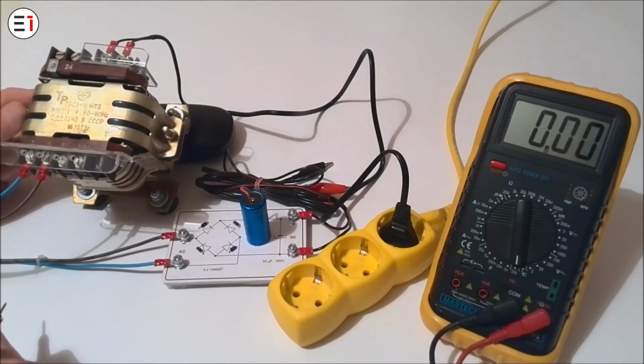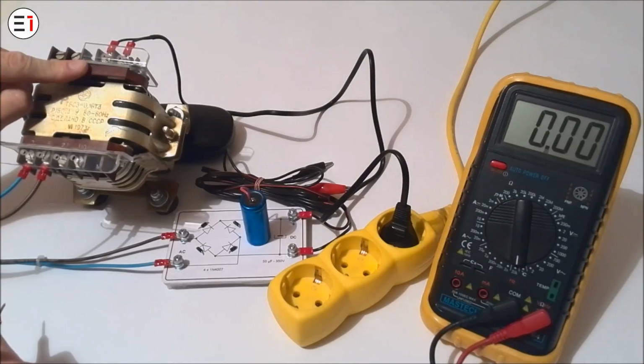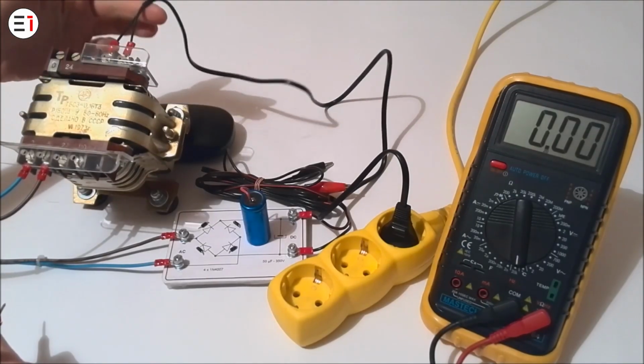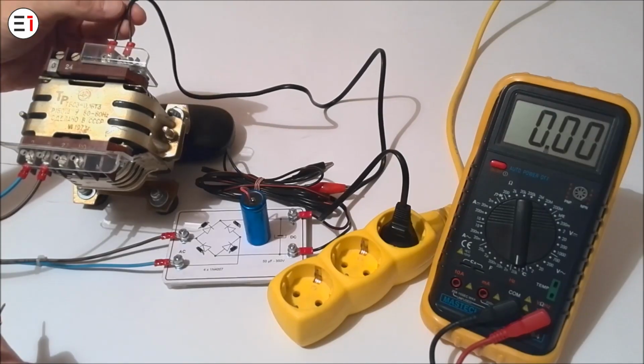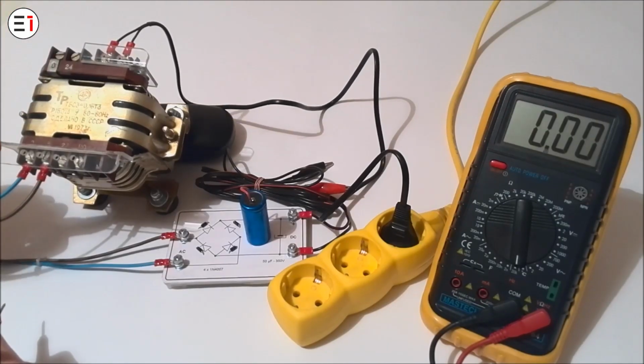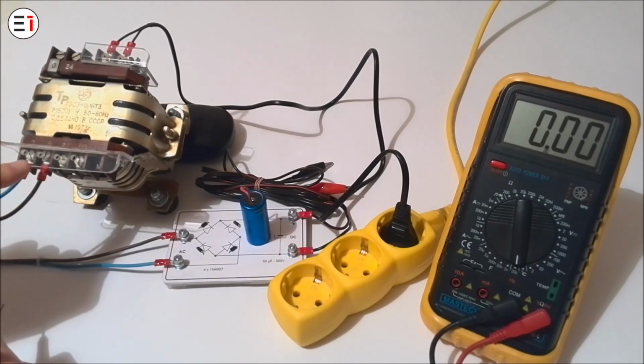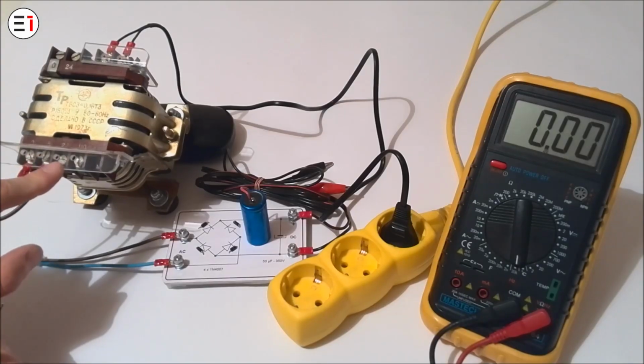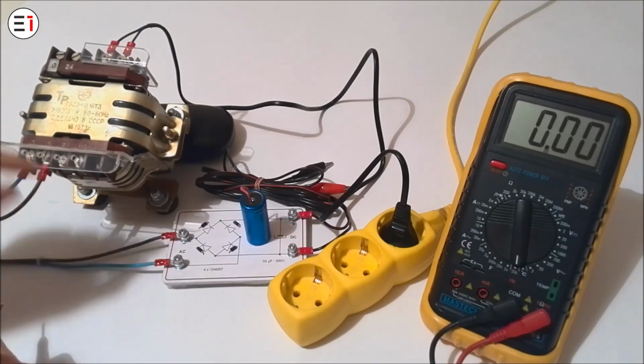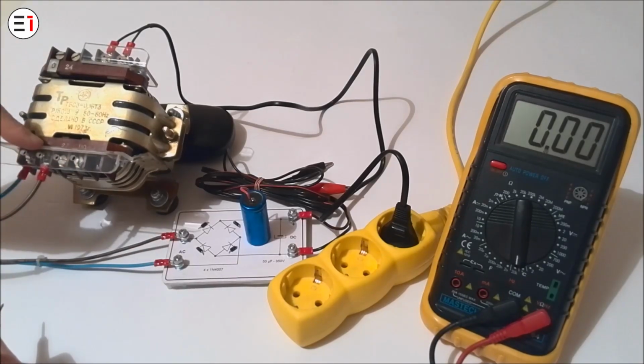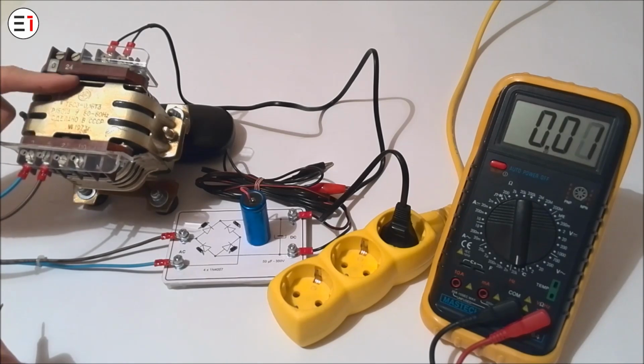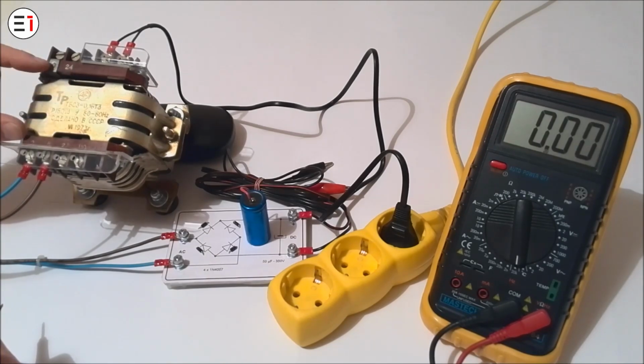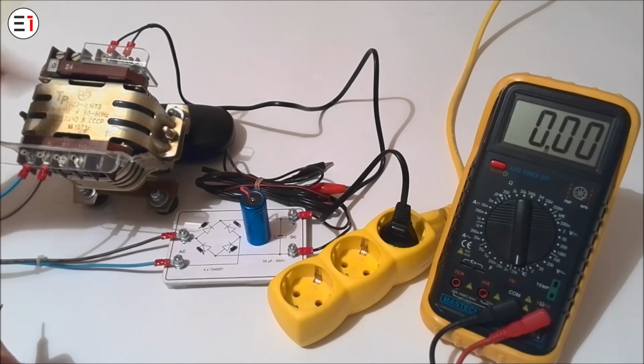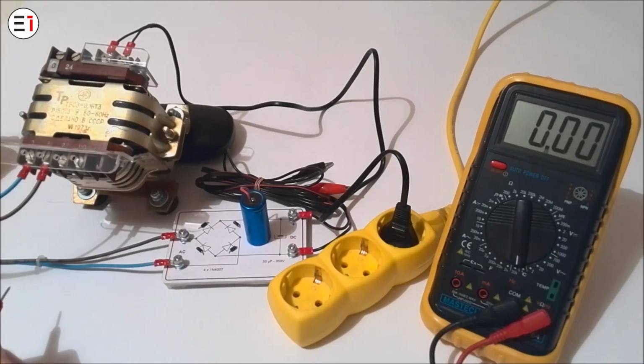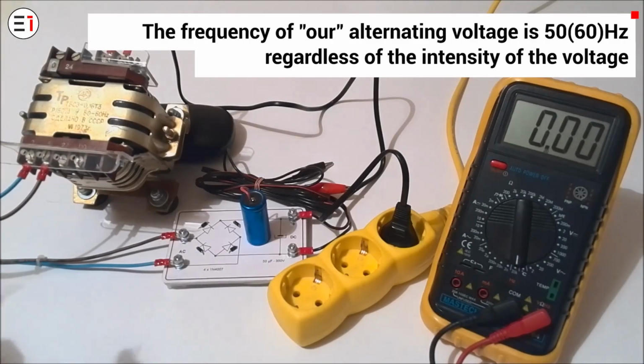Here we have a device called a transformer, and its role is to reduce the primary voltage, in this case the voltage between phase and zero, of 230 volts, to the voltage values that we can read here. Therefore, its purpose is to reduce voltages to 5 volts, 22 volts, and 110 volts. It should be known that even after the transformation, the voltage remains alternating, so the frequency remains the same as on the primary voltage.